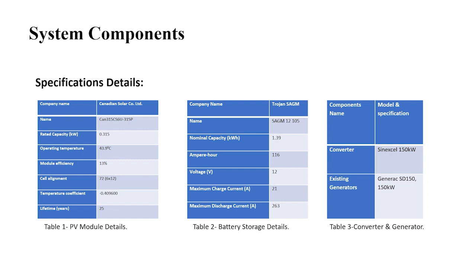Table 2 shows us the details of our storage system. We have chosen the battery from Trojan SAGM, with a nominal capacity of 1.39 kilowatt hour and an ampere rating of 116. It is a 12-volt battery with a maximum charge current of 21 ampere and a maximum discharge current of 263 ampere.